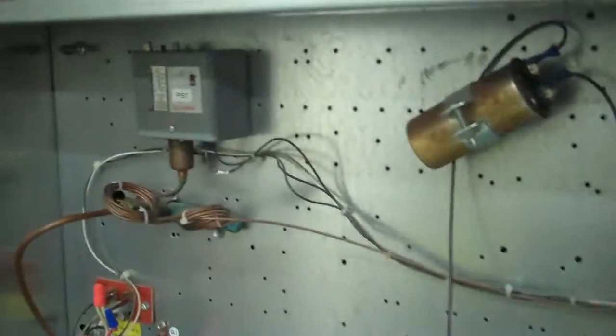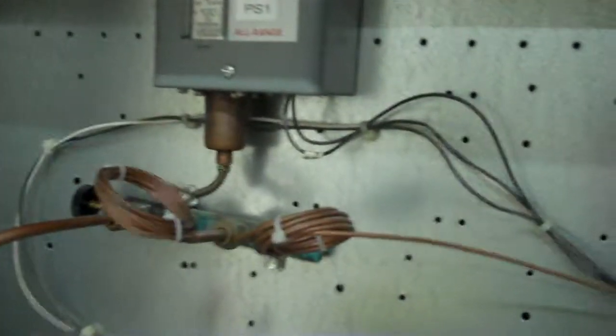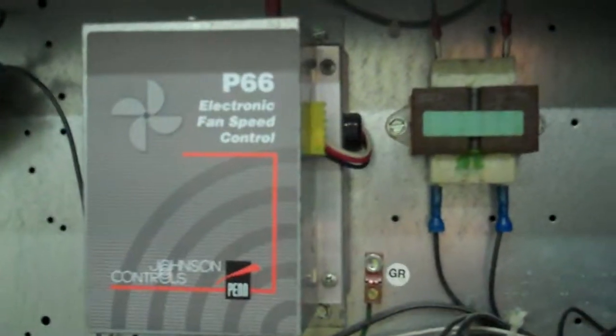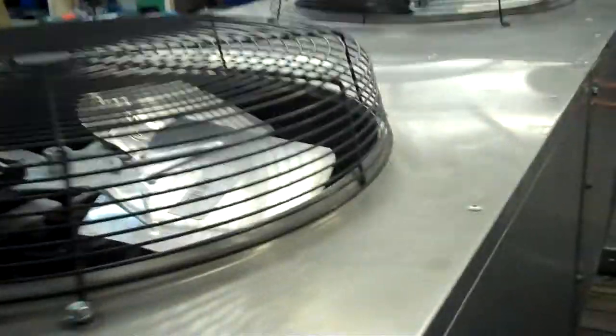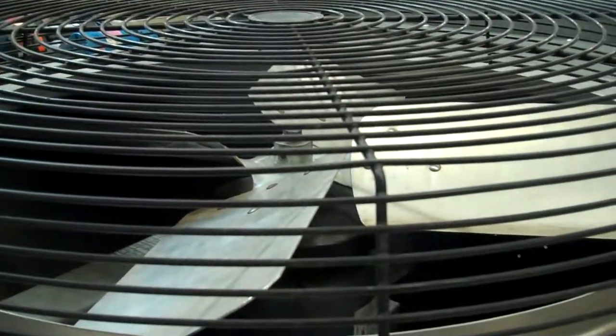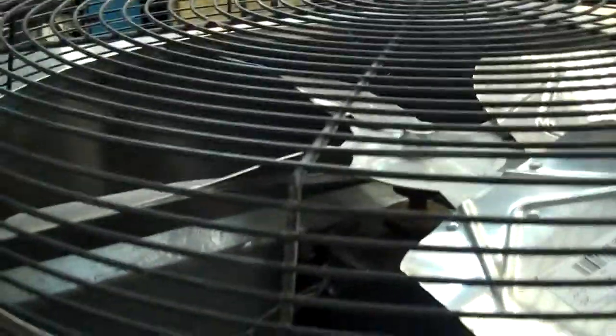Coming over to our remote air-cooled condenser. This is the inside of the control panel here. This is our pressure switch. It's nice that it has this, because this is going to be capable of low ambient operation outside. And we have the variable speed drive with a P66 electronic fan speed control. That controls one of the 2 fans. It happens to be the single phase fan, which is this one here, which is also the one that comes on whenever any compressor is running. And this here is our 3-phase fan, which will come on demand.